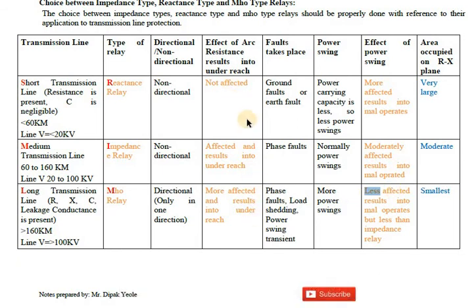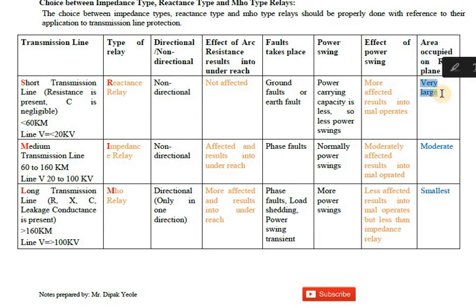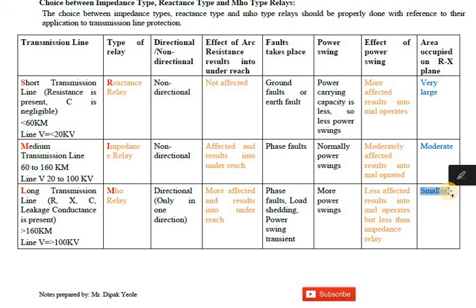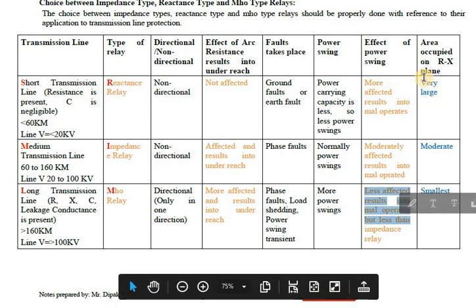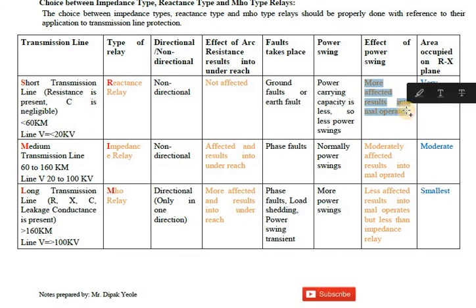On the R-X plane, the area occupied by each relay also explains these effects. The reactance relay covers the largest area on the R-X plane, the impedance relay covers a moderate circular area, and the Mho relay covers the smallest area. The larger the area, the more the relay is affected by power swings.